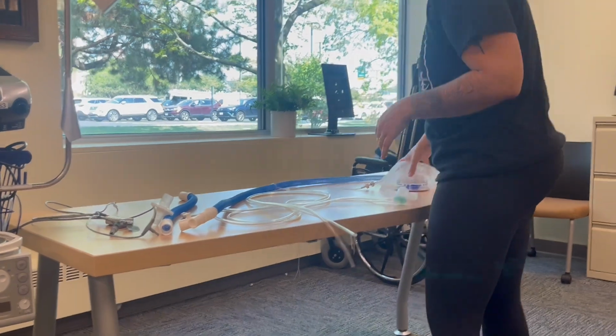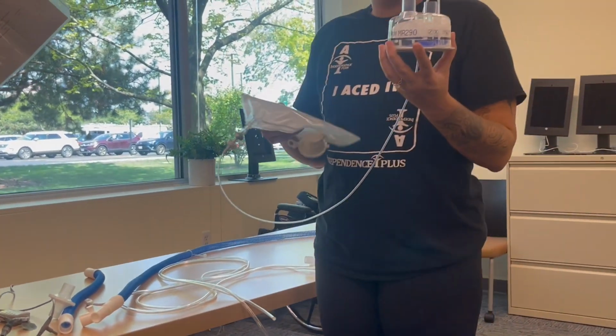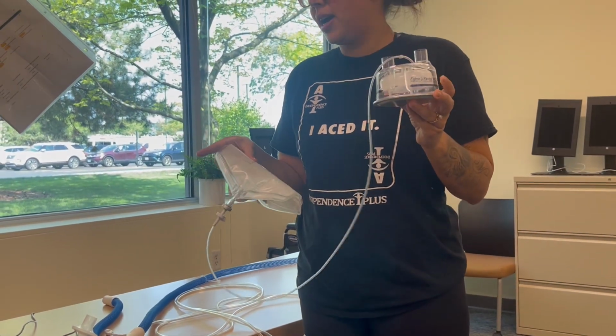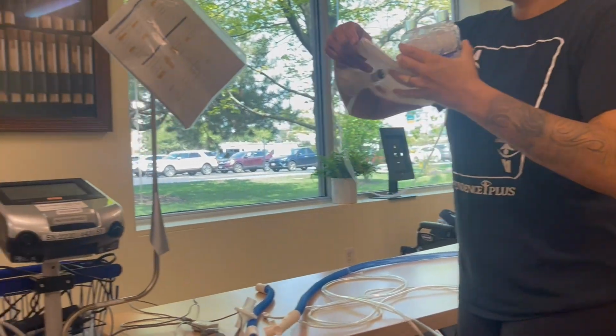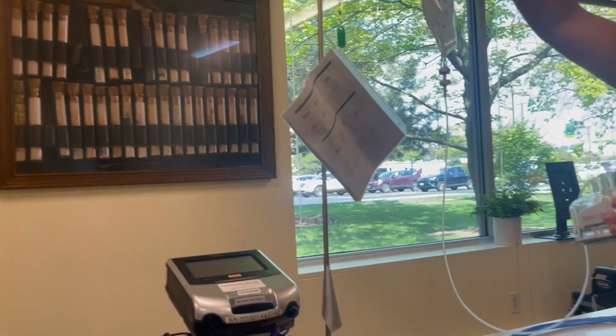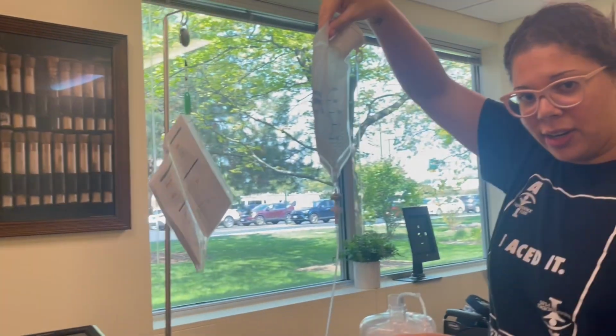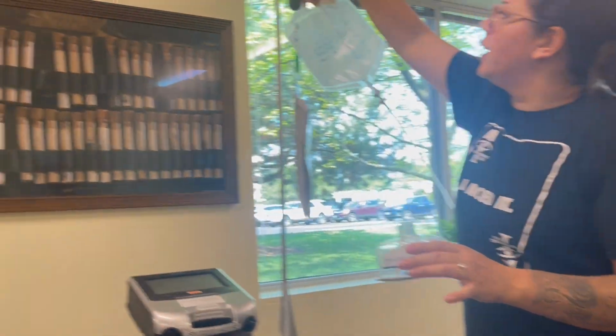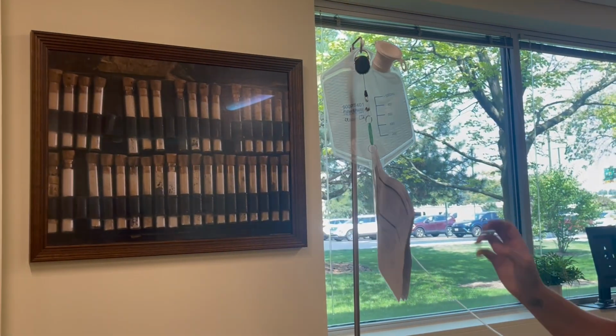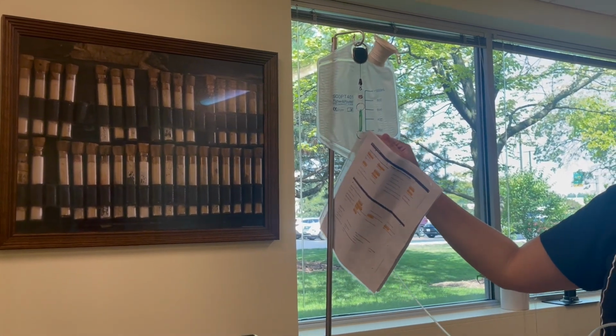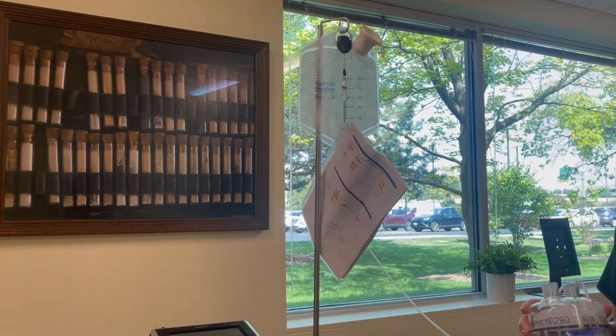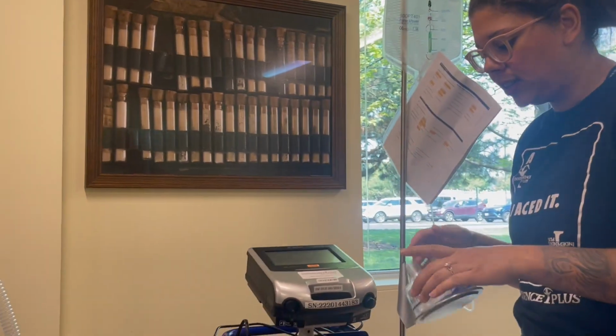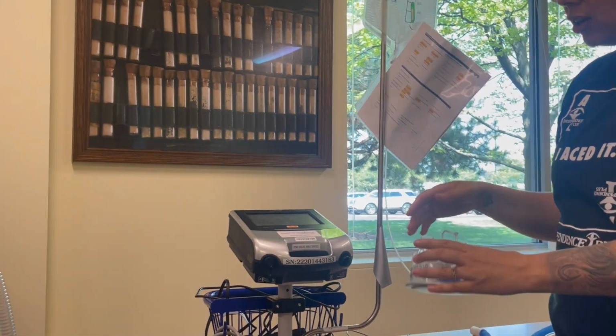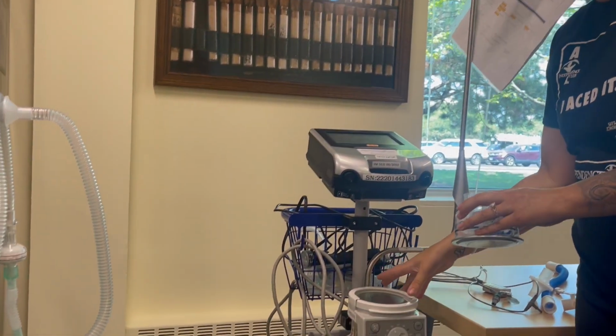So the first thing I'm gonna do is take my water chamber and connect that to my Fisher-Paykel machine. So here is my water bag. The water bag is connected to this water chamber right here. I'll go ahead and throw this on. This would be filled with distilled water, but right now I don't have it filled, so just keep in mind you would want water in this. As soon as I have water in the bag, it's gonna automatically fill this humidifier.